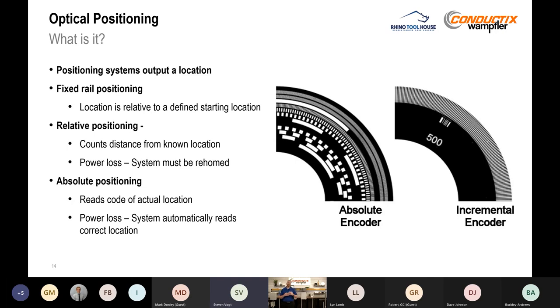A positioning system outputs a location relative to a starting point on a fixed rail. There are two types of technology. Relative positioning, similar to an incremental encoder, counts how far away from a known location — but if you lose power, it starts counting at zero again. So if you're at 30 feet and it turns off and back on, it thinks it's at zero. All of our systems are based on absolute positioning, which reads the actual location. So if I'm at 30.12 feet, power goes out and comes back — I know I'm at 30.12 feet as soon as I power on.